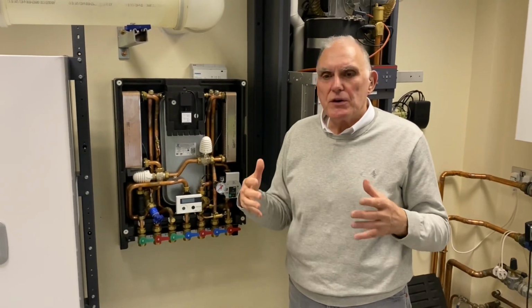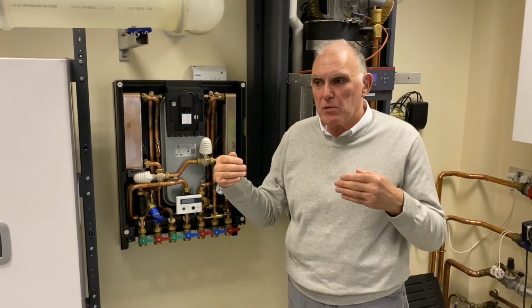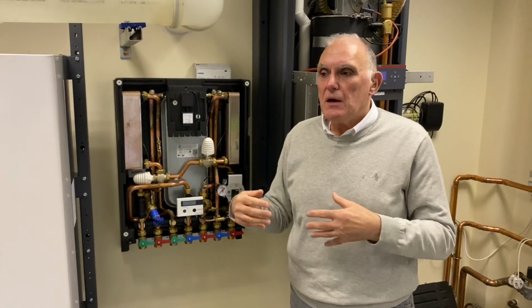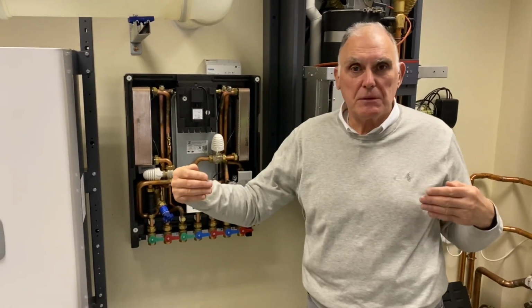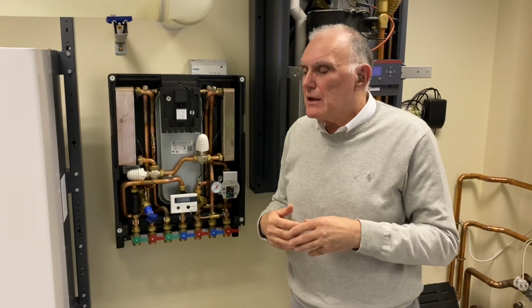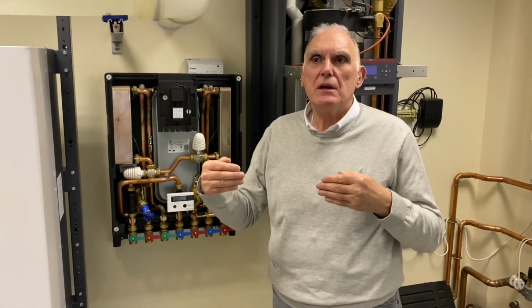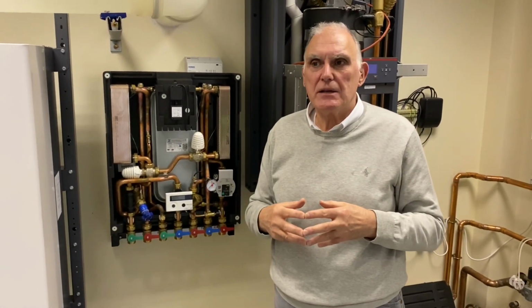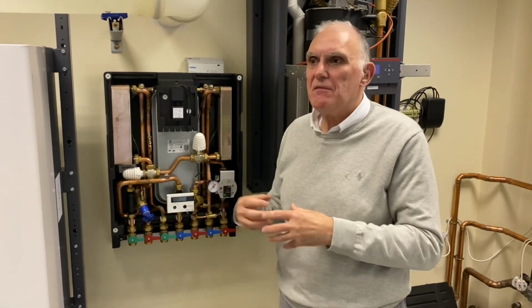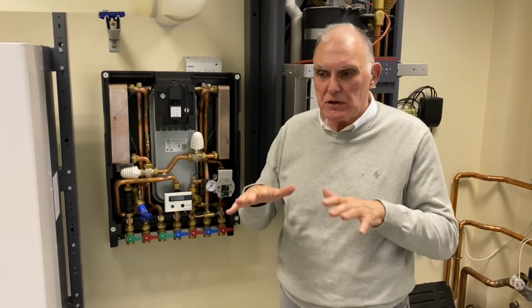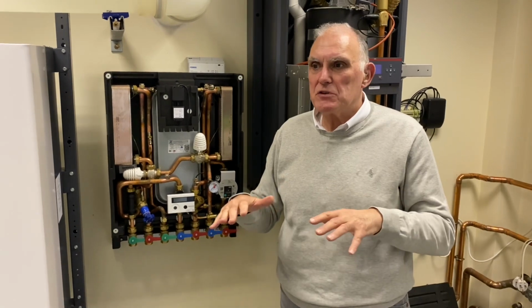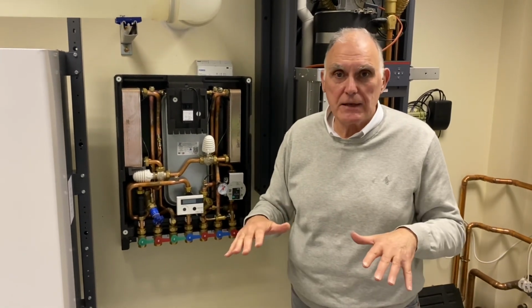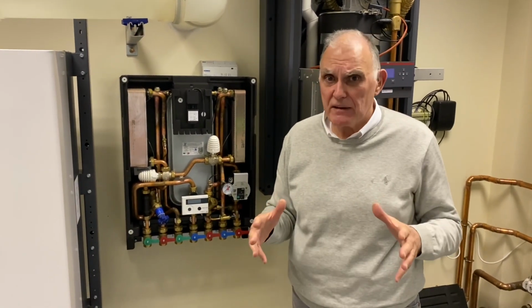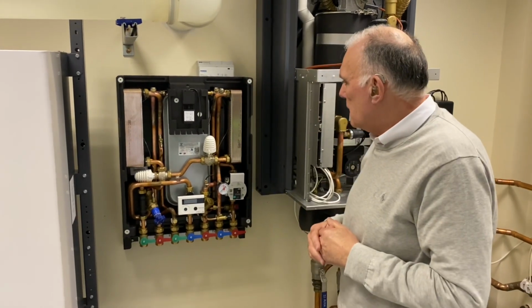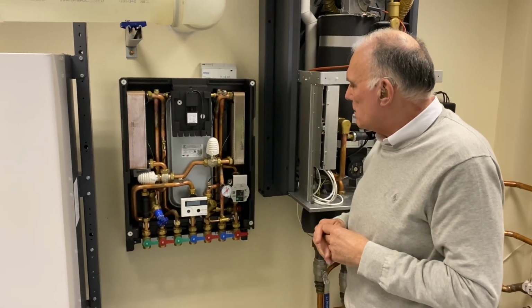Now that limits what you can do. It's obviously going to be operating at a high temperature because the water's had to travel some distance from the plant room. So you'd be restricted to perhaps using low surface temperature radiators or putting mixing and blending valves in beneath the unit to make sure that the surface temperature of radiators or underfloor heating would be at safe levels. But as I say, this is direct.